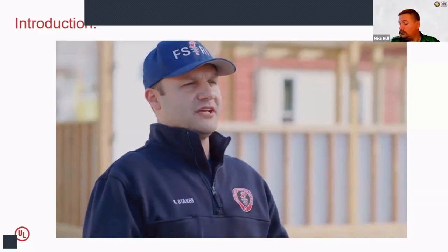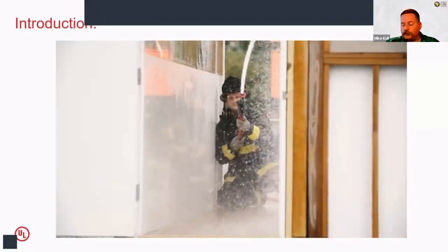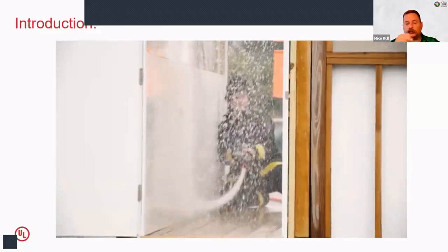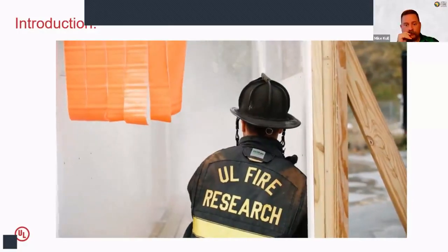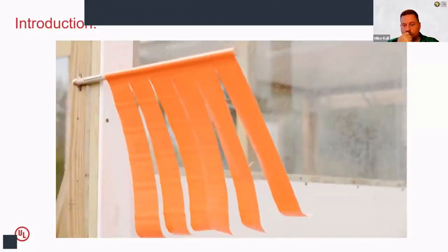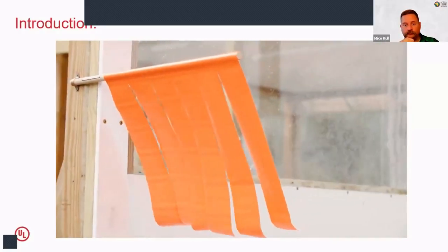If we visualize how many droplets make up a typical hose stream from either a smoothbore or combination nozzle, the potential impact and magnitude of air entrainment should be clear. In short, how we manipulate a hose stream inside a structure can change the amount of air that is entrained and has the potential to significantly affect fire dynamics and victim survivability during suppression. Now let's take a look at water mapping, or how water is distributed within a compartment.